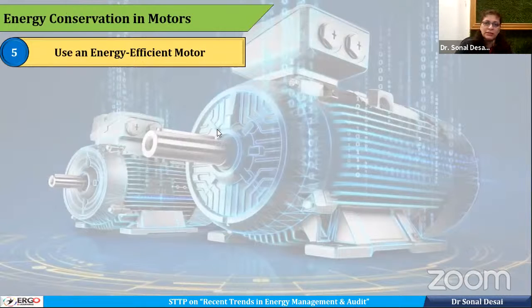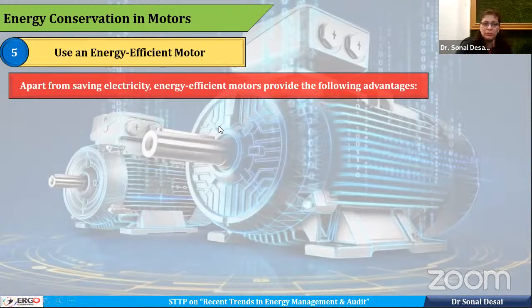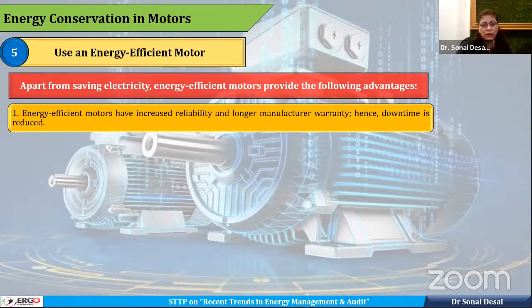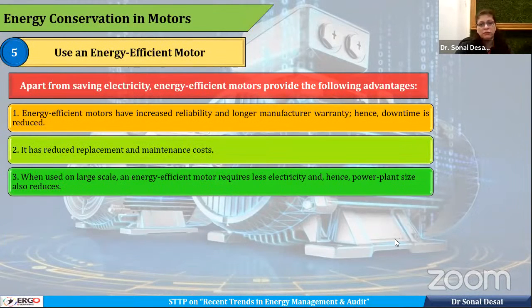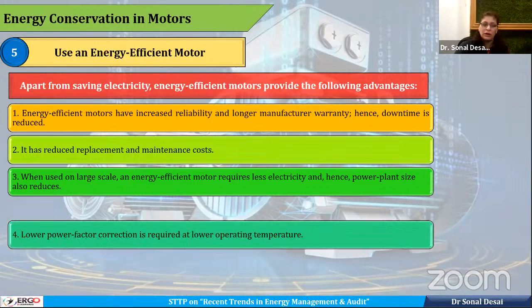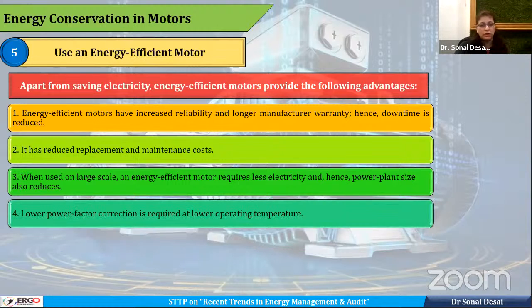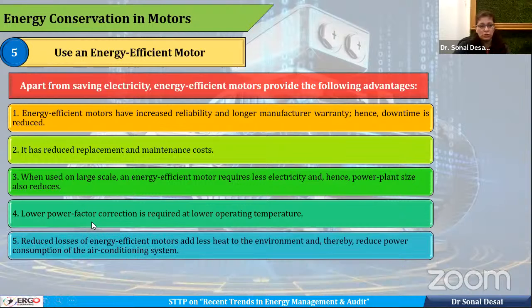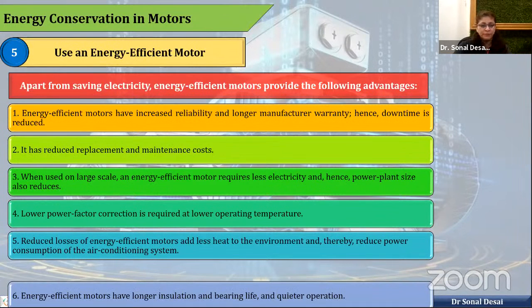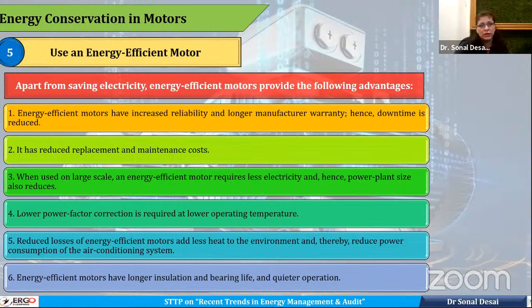Apart from saving electricity, when we go with an efficient motor or a super efficient motor, it has multiple advantages: more reliability, longer manufacturer warranty, less downtime, and reduced replacement and maintenance cost. On a large scale, they use less electricity, hence power plant size will be reduced. So if many people replace their motors with efficient ones, the overall power plant capacity requirement will reduce, and the fuel burden will also reduce. It will reduce the power factor correction requirement, so that cost is also saved, and reduce losses in the motor and heat released to the environment, thereby reducing power consumption of systems like HVAC or cooling tower, and give better bearing life, quieter operation, and many more.